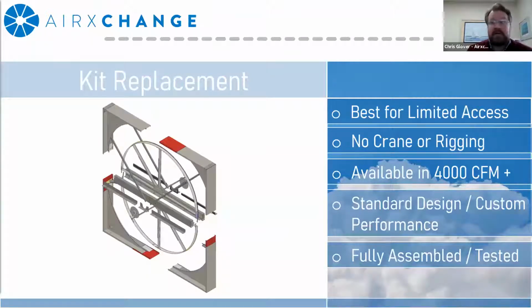In most cases, it completely eliminates the need for a crane or any type of building or unit modification. And this can be quite a big deal because if you're trying to replace a monolithic wheel, these large monolithic wheels can sometimes put you in a position where you're looking at removing sections of a roof or an entire section of an air handler. Also, you have to take into consideration any rigging or preparation, which could also be added to the labor. This kind of eliminates all that cost and complexity.